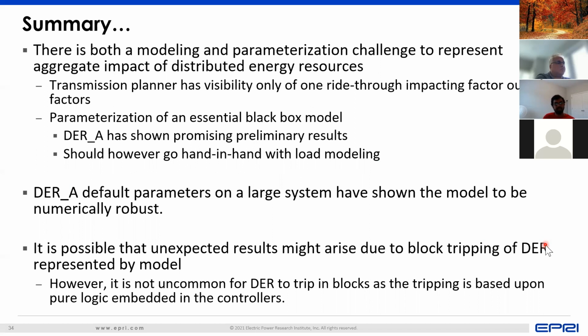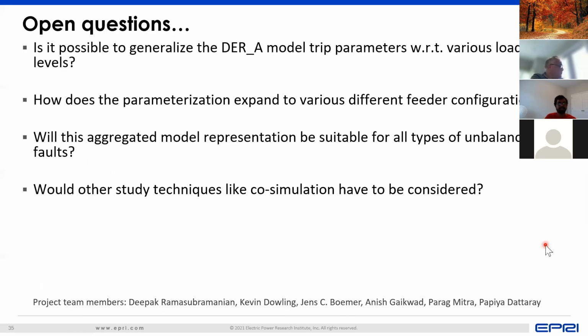They're by no means, however, a closed set of generalized parameters. There's still more research work to be done. There's a lot of work to be done to understand the interaction between load and DER and how they may impact the behavior of DER and the aggregated model. So that's something that we're still continuing to work on. And it's possible that at the transmission side, we could get unexpected results with DER tripping in blocks, but it's not to be considered as something which is a simulation artifact, because in reality, DER may actually trip in blocks, and it's important for us to consider that in our planning studies.